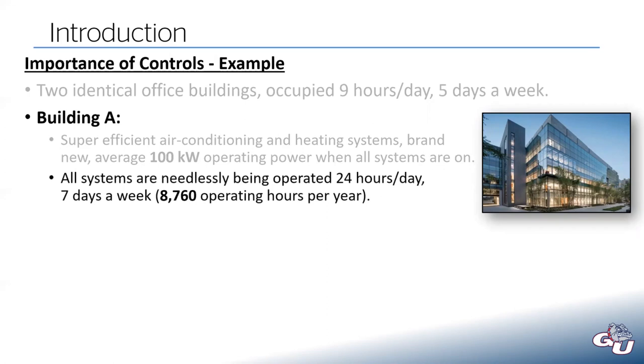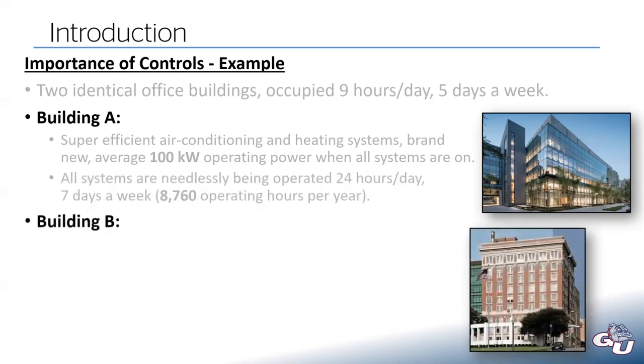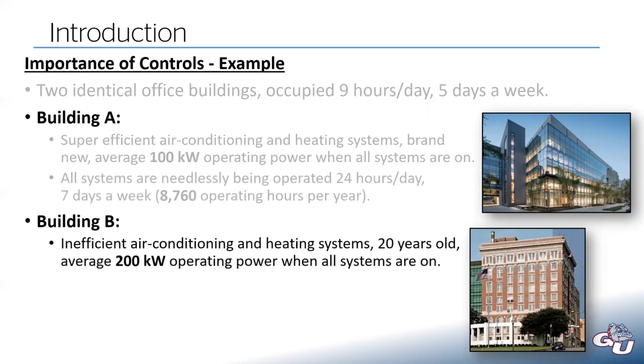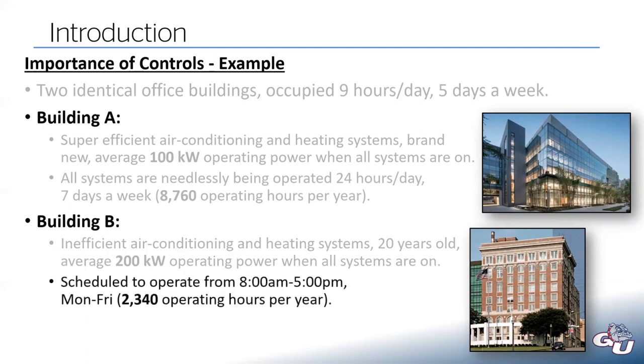But what if all those systems are being operated 24 hours a day, 7 days a week, even though the building is only occupied 9 hours a day, 5 days a week? The second building, building B, well, let's say they have very inefficient air conditioning and heating systems. Everything's at least 20 years old. And on average, when everything's running in that building, it's using 200 kW of operating power. But let's say that building is scheduled to operate on a tight schedule from 8 a.m. to 5 p.m. Monday through Friday, which is about 2,300 operating hours per year.